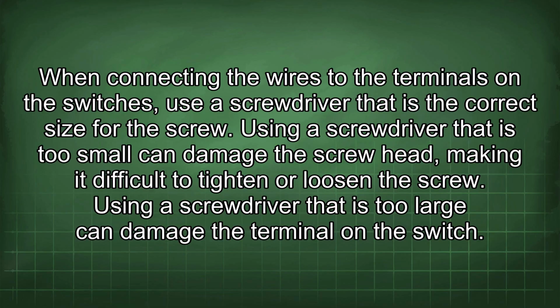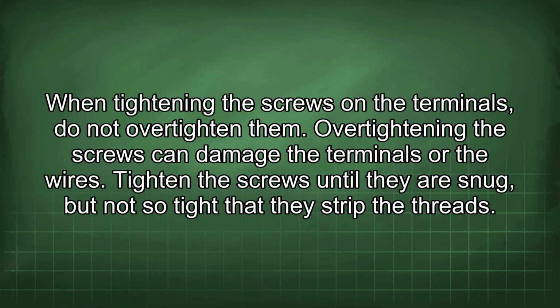When connecting the wires to the terminals on the switches, use a screwdriver that is the correct size for the screw. Using a screwdriver that is too small can damage the screw head, making it difficult to tighten or loosen the screw. Using a screwdriver that is too large can damage the terminal on the switch. When tightening the screws on the terminals, do not over-tighten them. Over-tightening the screws can damage the terminals or the wires. Tighten the screws until they are snug, but not so tight that they strip the threads.